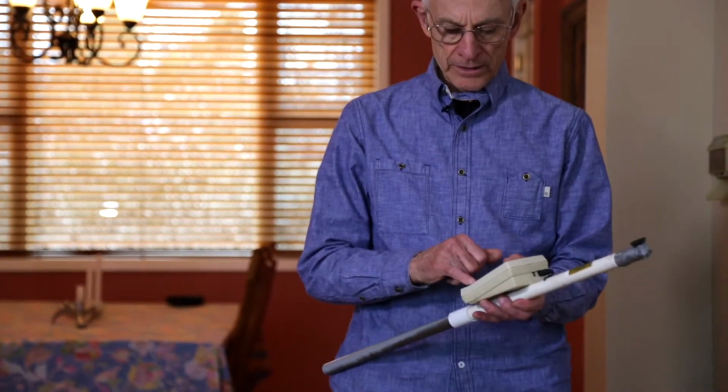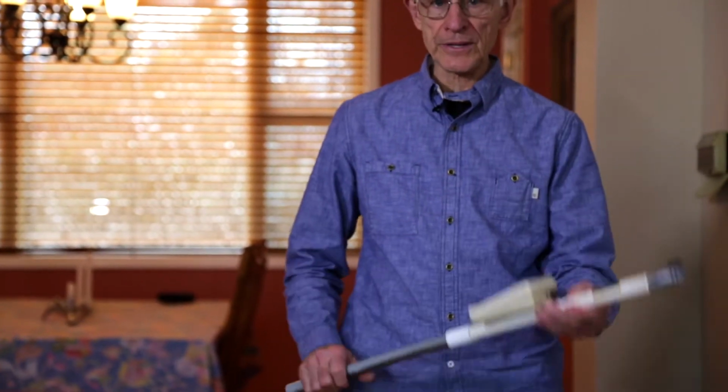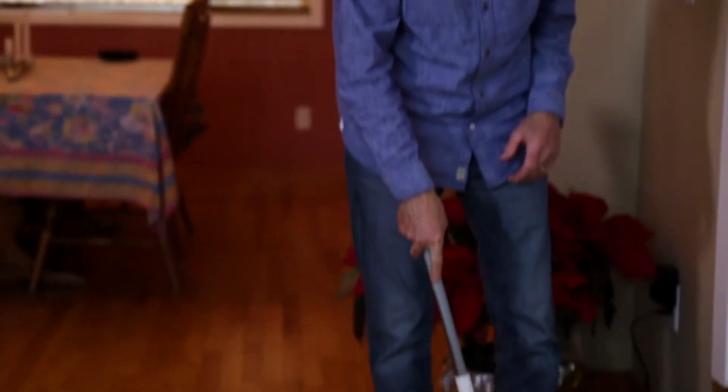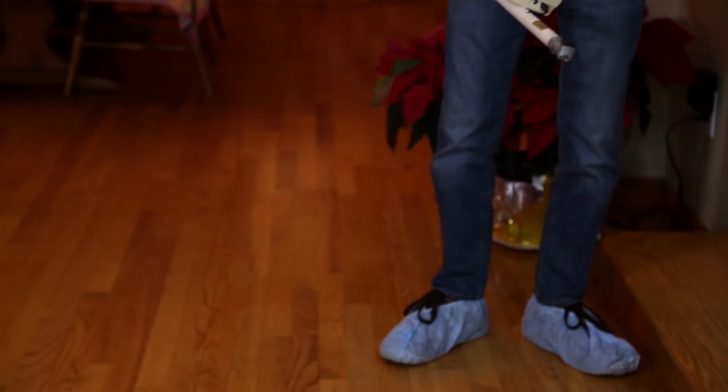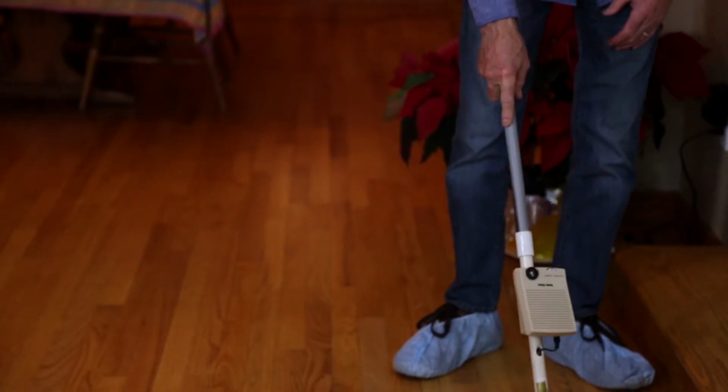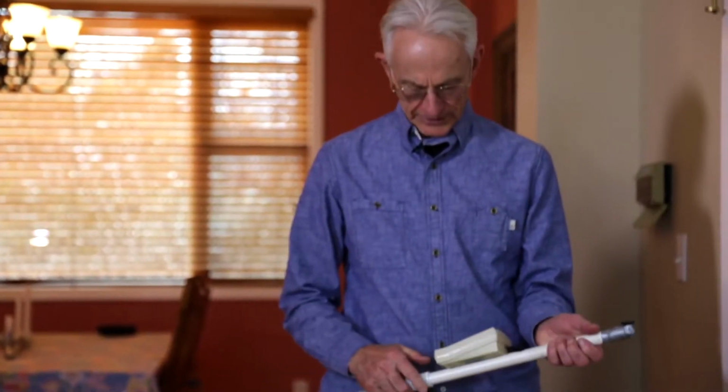So I'm using a buzz stick, which is something that can do a quick survey, and we've been able to locate in the floor an area which has high magnetic fields, and subsequent investigation of that has shown it to be a water pipe downstairs. We turned off all of the power for the house by shutting off the main circuit breaker, and we still had the magnetic field on the floor and the current flow coming in on this water pipe that is being seen upstairs as a magnetic field.